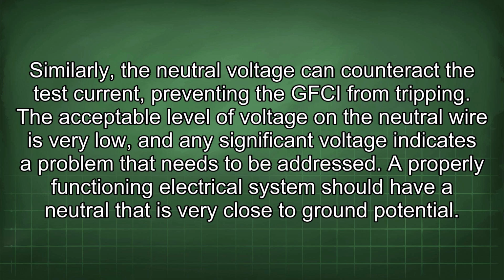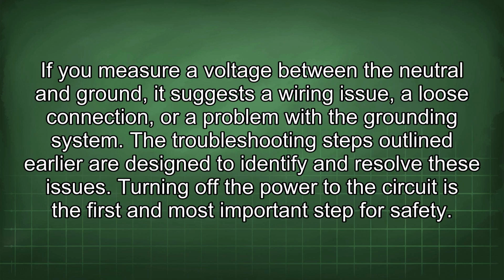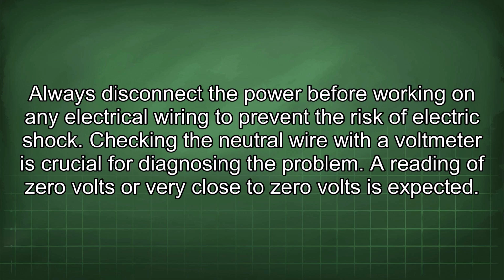The acceptable level of voltage on the neutral wire is very low, and any significant voltage indicates a problem that needs to be addressed. A properly functioning electrical system should have a neutral that is very close to ground potential. If you measure a voltage between the neutral and ground, it suggests a wiring issue, a loose connection, or a problem with the grounding system. The troubleshooting steps outlined earlier are designed to identify and resolve these issues. Turning off the power to the circuit is the first and most important step for safety. Always disconnect the power before working on any electrical wiring to prevent the risk of electric shock.